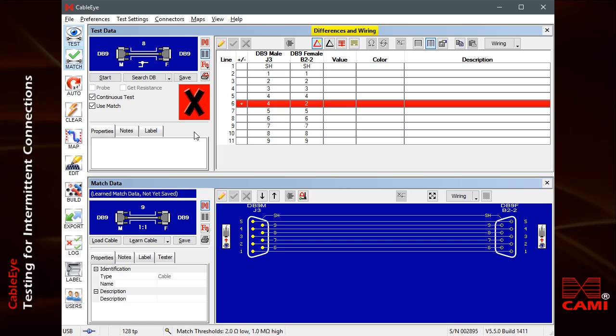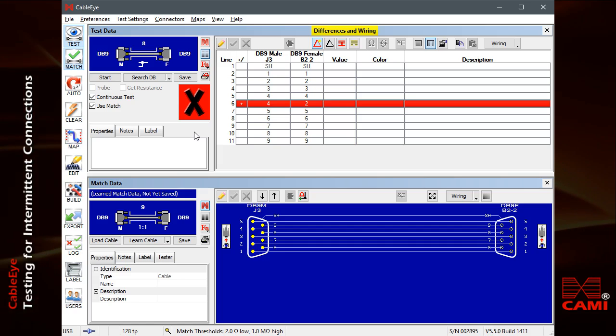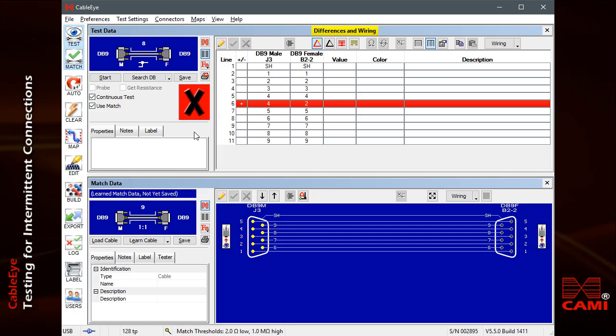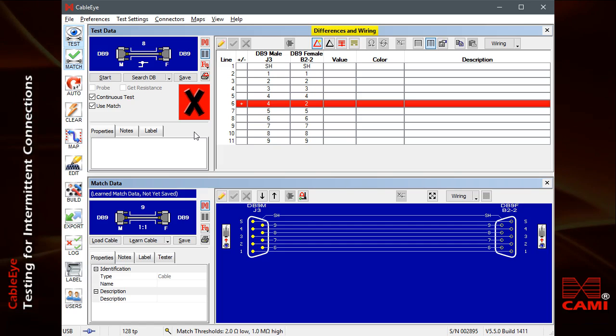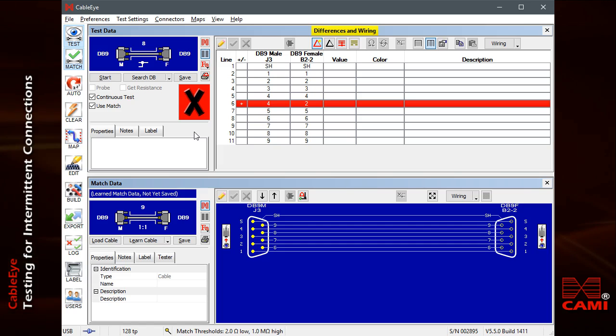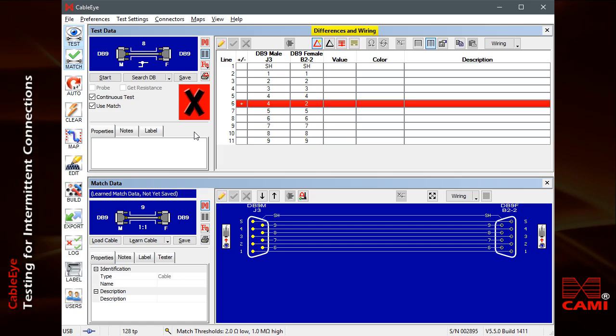During one cycle, every test point is measured with respect to every other point, thus checking every wire in the cable for an intermittent connection, as well as for potential shorts to any unused pins that you may have on the connector.